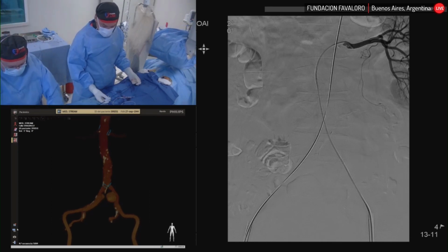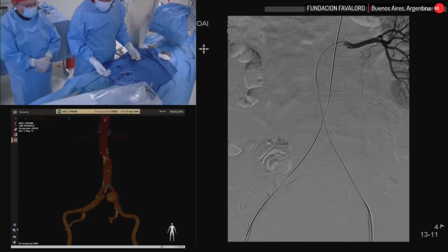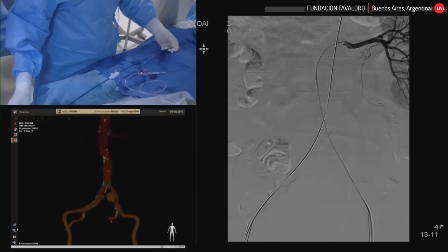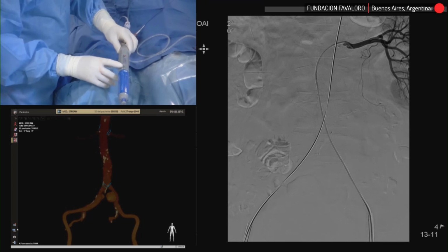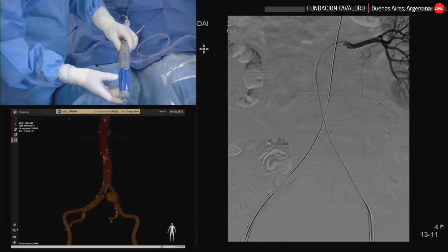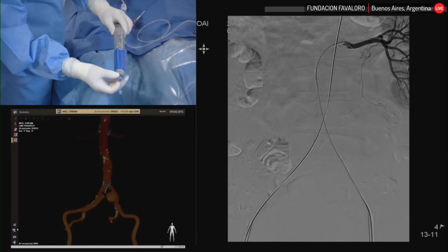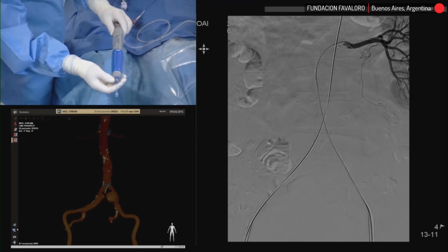The device also has an inline sheath that we are going to disengage when we complete the delivery of the device. This is the delivery system. So this is the security mark that's going to be moved forward, and then I can start rotating to deliver the device very slowly. And when we are finished, we have to disengage the proximal hooks of the device for the proximal fixation.